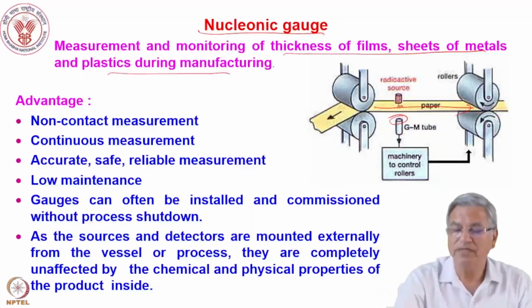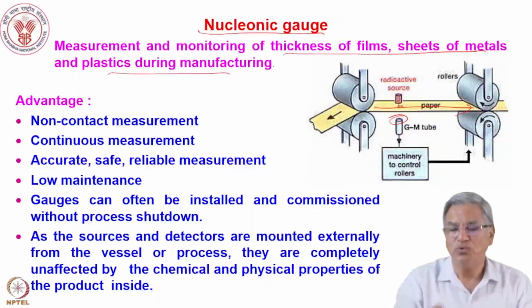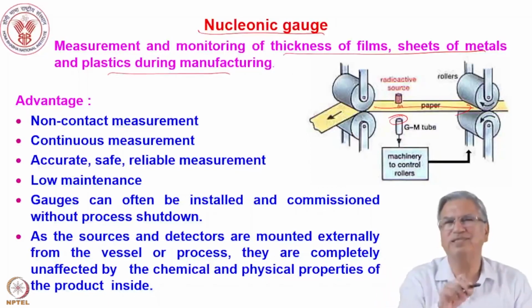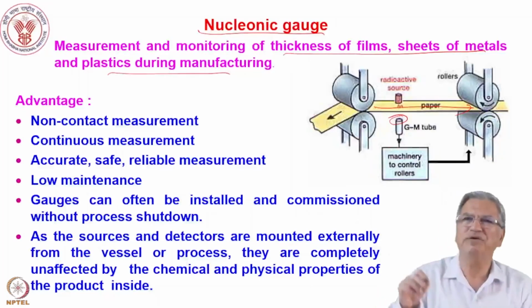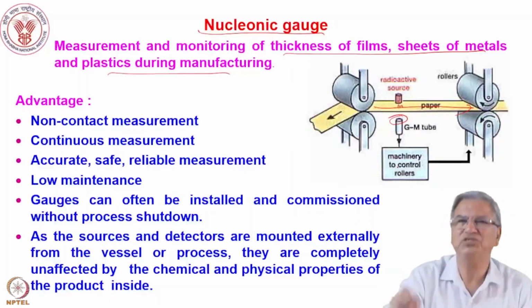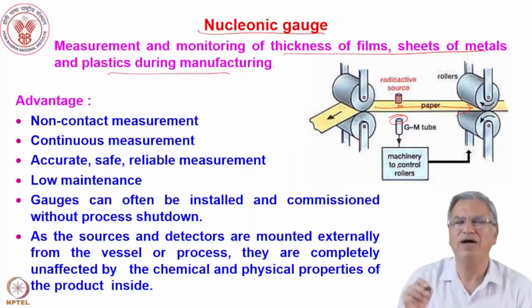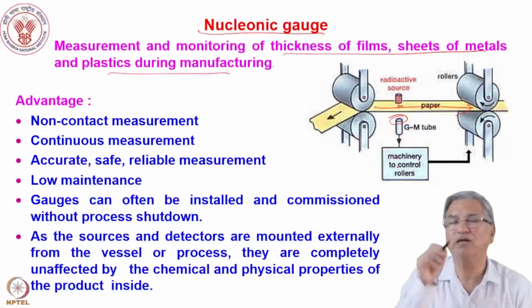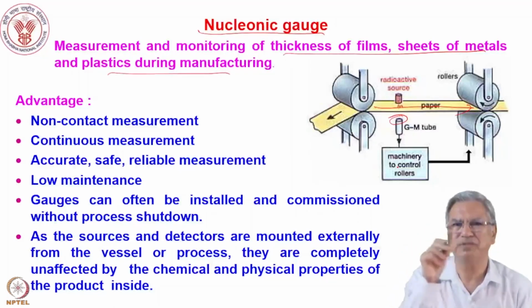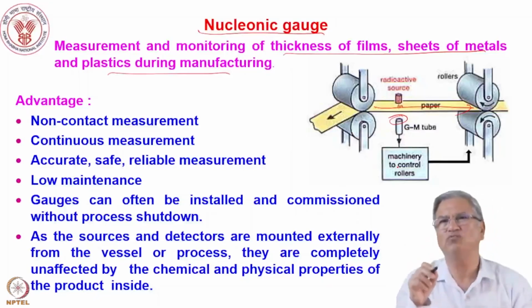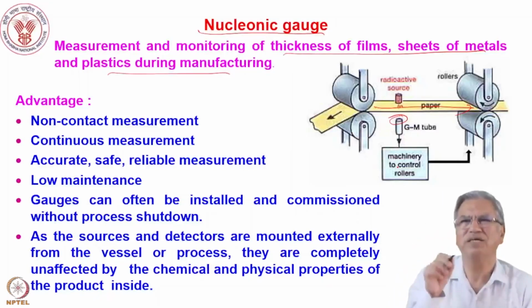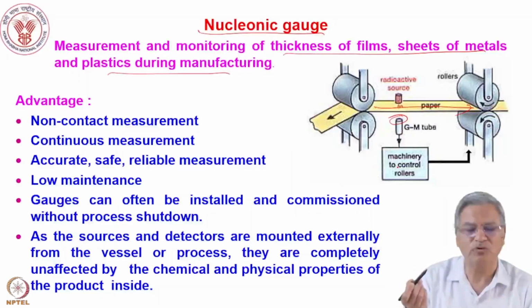Then you measure the activity as a function of time. If the thickness is constant, you get constant activity in the counter. But whenever there's a change in thickness, that intensity changes. Beta and gamma can be used to find the change in thickness, whereas for alpha, with very thin foils, micron thick, you use the change in alpha energy, because alpha intensity won't change with thickness, but alpha energy will. So for very thin foils, micron thick or less, you use alpha, and for millimeter thick, a couple of millimeters, you use beta or gamma sources.